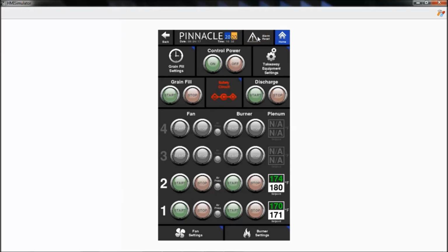There's another type of alarm called a cool down alarm. If you can pull the e-stop back out. Okay, so we've reset our e-stop and cleared the alarm by clicking on the alarm reset button. If I now turn on my control power, in this instance I'm going to start my fan. Can we get air pressure? And I'll start a burner as well. So we've satisfied air pressure. I'll turn on burner number 1.